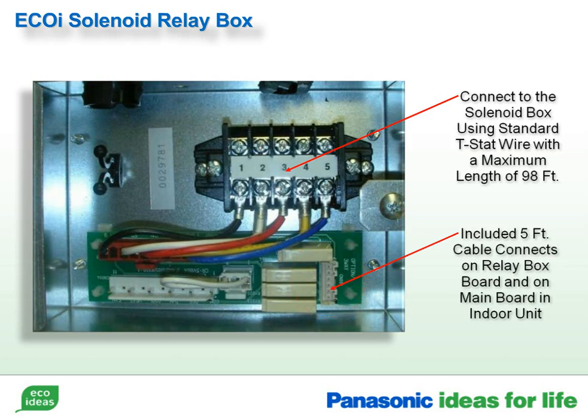Connect the gray cable into the 3-way plug on the air handler's circuit board, and plug the opposite end into the relay box. Please note, there might be an existing cable plugged into the 3-way connector, located on the air handler's circuit board. If so, plug your gray cable into the end of this existing cable. On terminals 1 through 5, attach 18-5 wire, and run this to terminals 1 through 5 of the solenoid box. This connection is polarity sensitive. Do not cross these wires because the solenoid box will not operate properly. The 18-5 wire required for this connection does not have to be shielded.